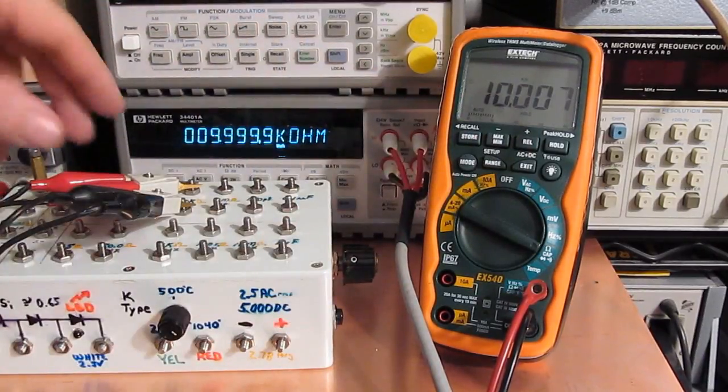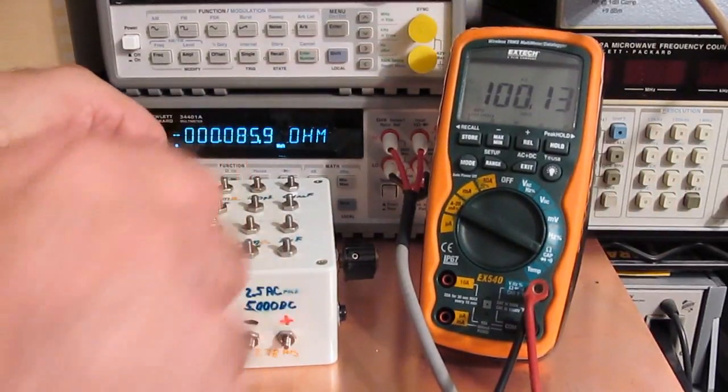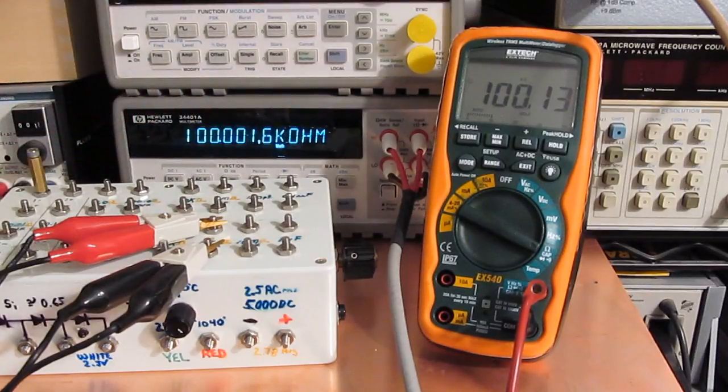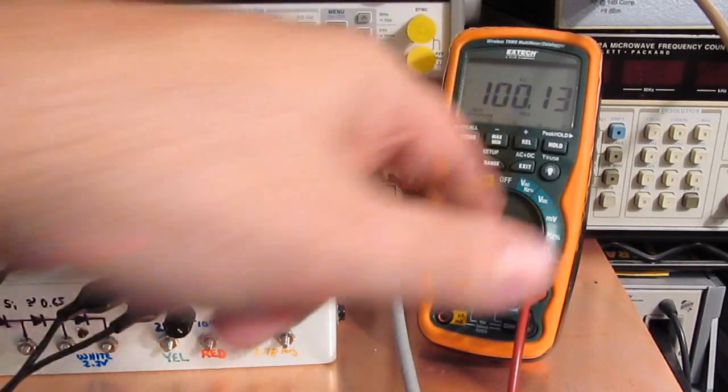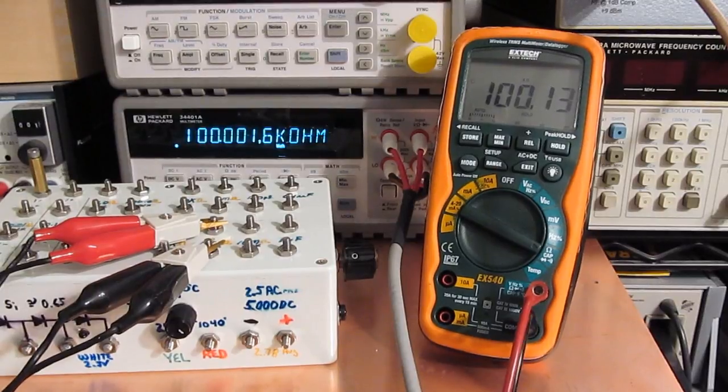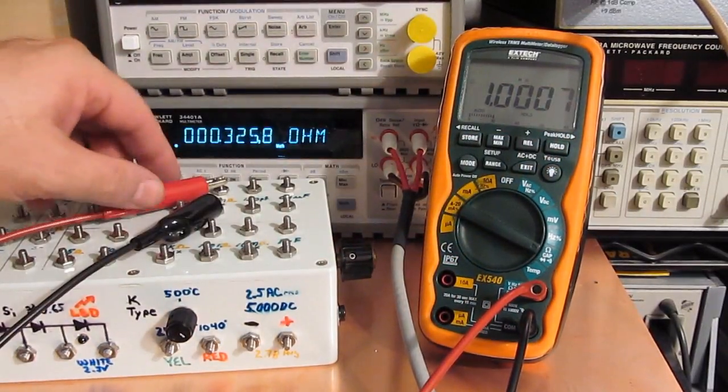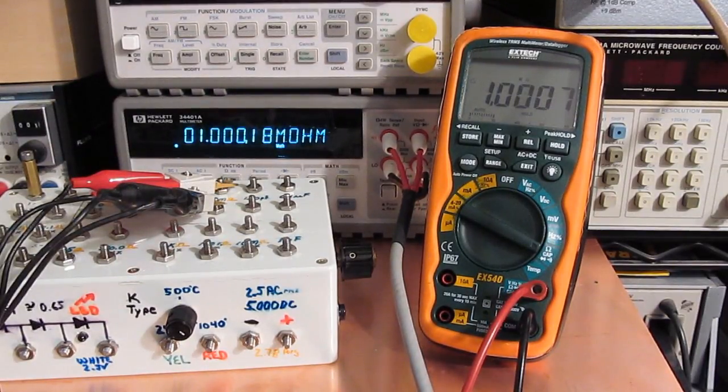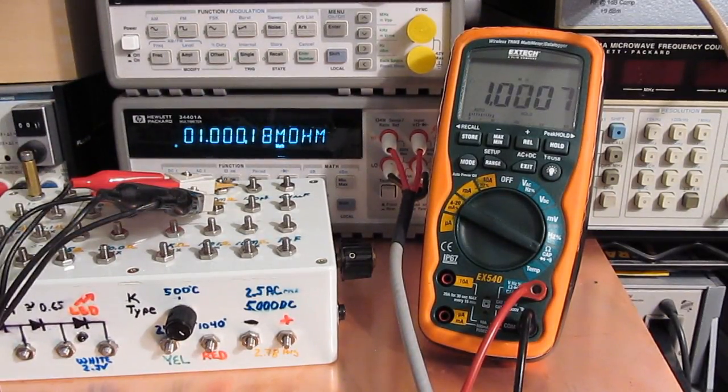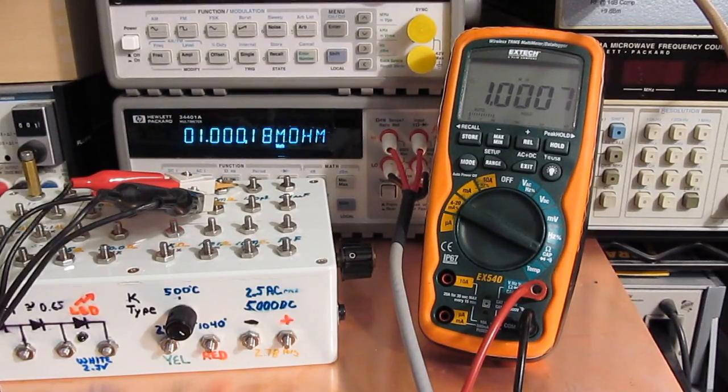Looks like the hundred k reads a little high, so it's 100.13 and again the HP is 100.0017, still fairly close. This is with a one megohm resistor. Let's see on our HP, it's 1.00018 meg versus 1.0007 on the Extech, still pretty good.